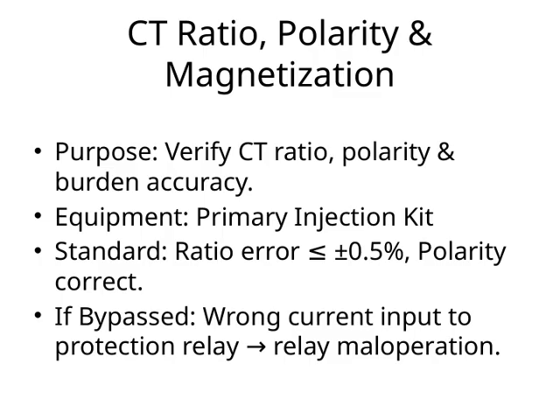The ratio error should be within plus or minus 0.5%, and the polarity must be correct. Why does this matter? Well, if the CTs are bypassed or connected improperly, it can send the wrong current input to the protection relay. This can lead to relay maloperation, meaning the protection system might not act when it should, or it could trip unnecessarily.